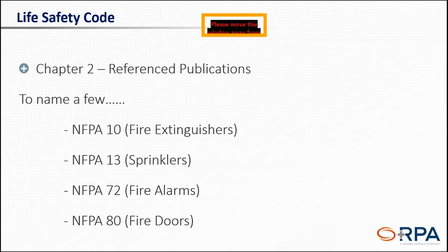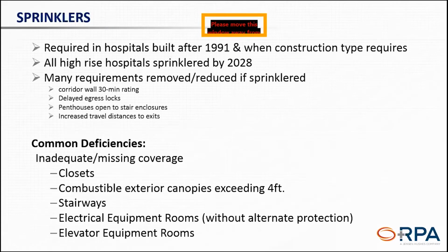So where are some of the specific changes? For instance, NFPA 80 for fire doors: the big difference from the previous edition, the 1999 edition of NFPA 80, to the reference standard of 2010, is that now we have to perform our annual fire door inspections. That's a big difference from the previous edition. That one's been talked about quite a bit, but that's just one example of one change in one text. So you can imagine the different levels of changes that have occurred in each of these. And we're going to touch on a few of these.